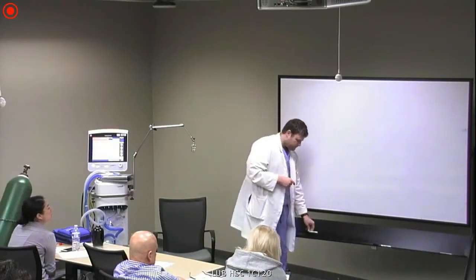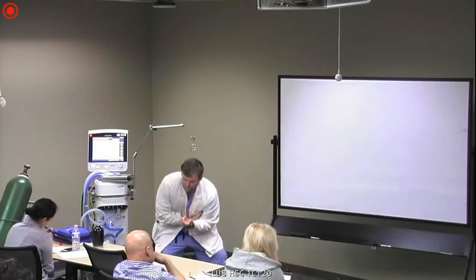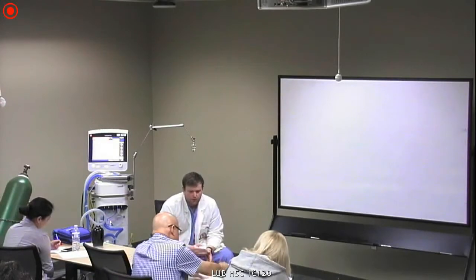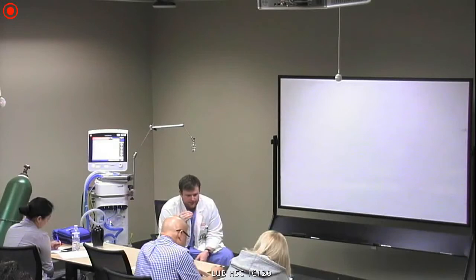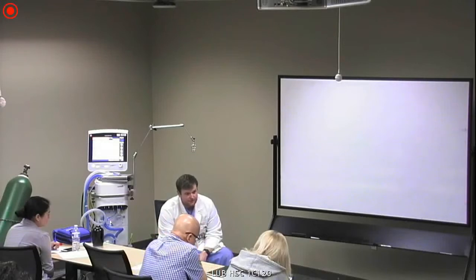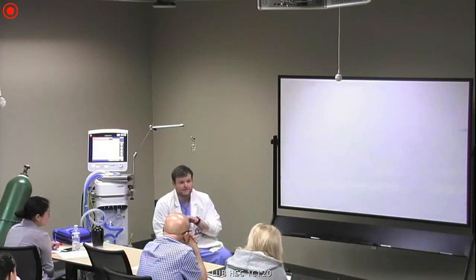With PRVC, you start as pressure, so you get that variable flow to start with. It will finish that initial inspiratory flow setting and then read back how much volume has been delivered. Depending upon how much volume you've gotten, it will then give the next amount that's needed to reach that volume as additional volume.